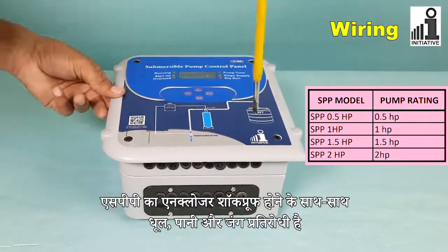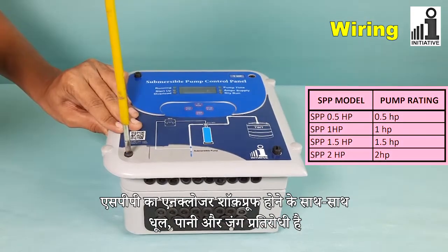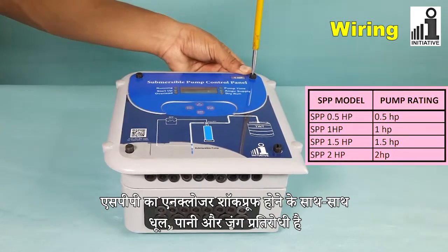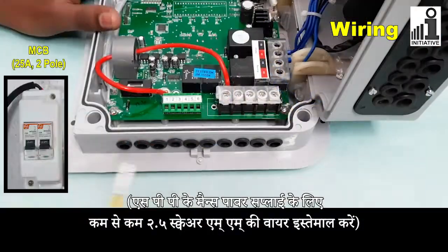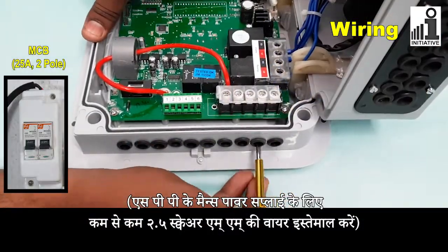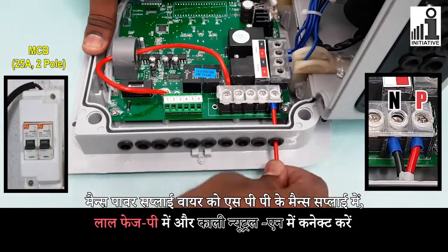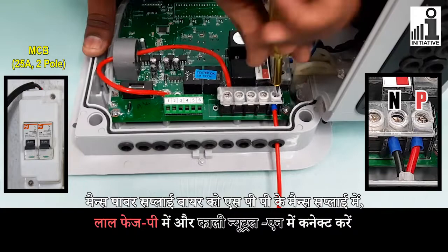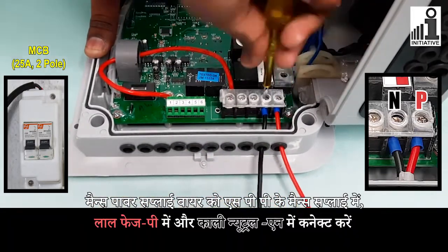The enclosure of SPP is shockproof as well as dust, water, and corrosion resistant. Use minimum 2.5 square mm wire for SPP's main power supply. Connect main power supply wire in SPP's main supply's red Phase P and black Neutral end connectors.